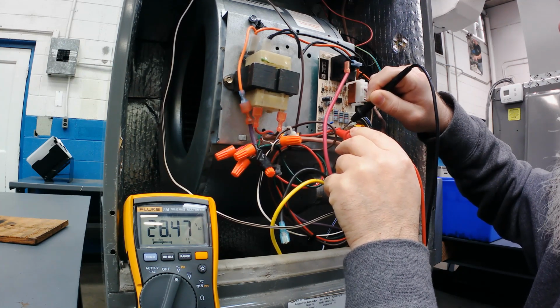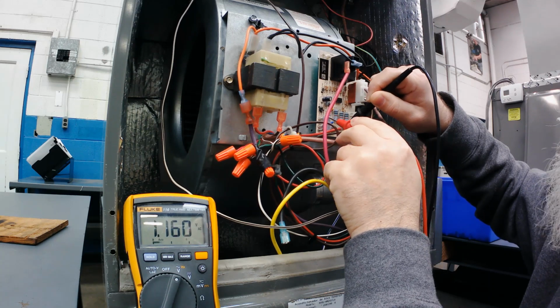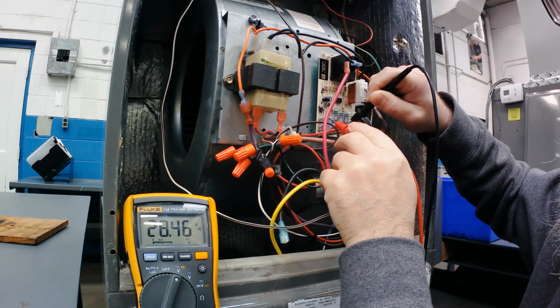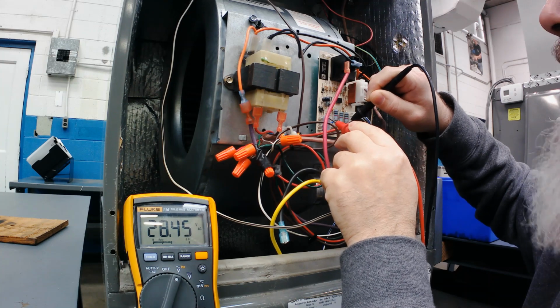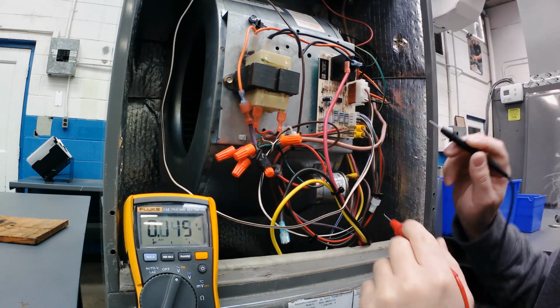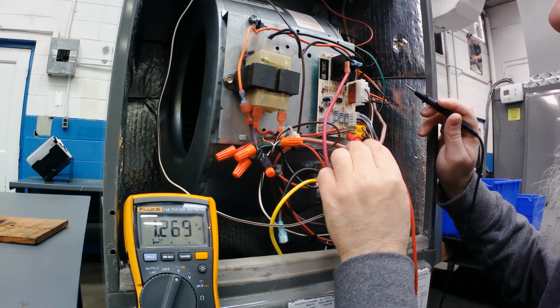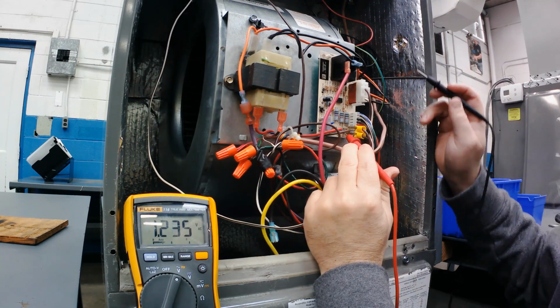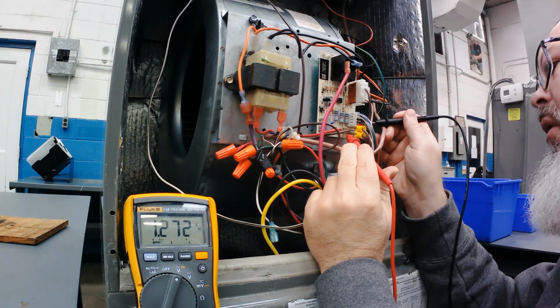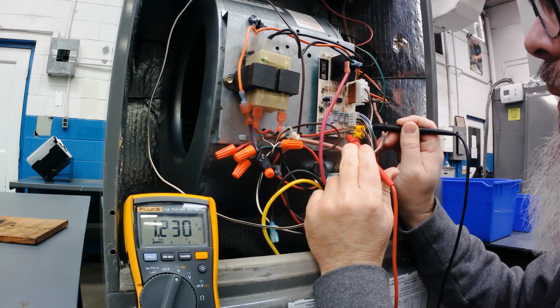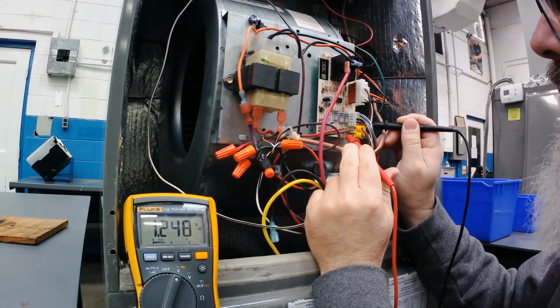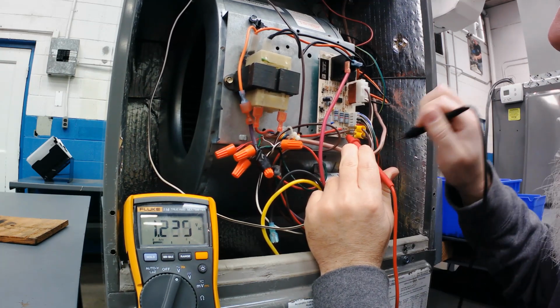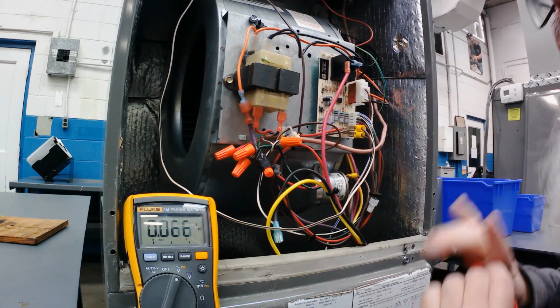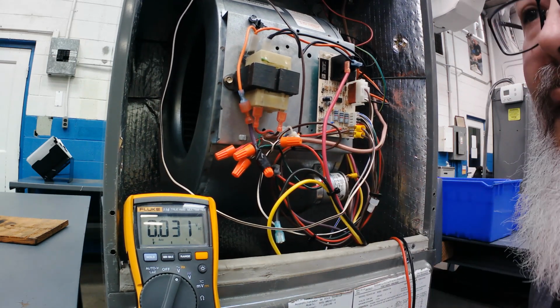If the fuse is good, I'm going to go across the fuse to the other side. Hey, look at that, my fuse is good. And that's going back in the board, and is going to go over here. I'm going to swap leads, but I'm going to keep one on that transformer common. It's going to go over here to this R that's leaving our circuit board. Okay, so this is a very tight plug. You can't get in there. Let me show you what I would do in this instance.